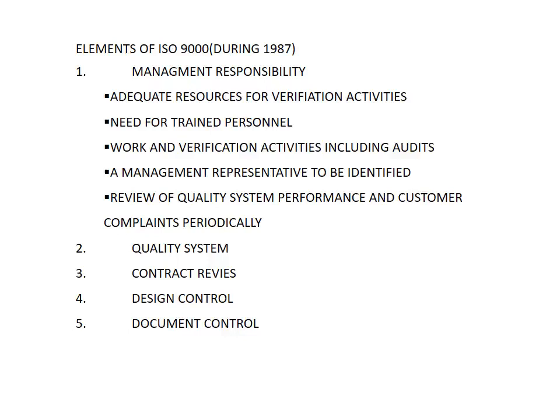The internal verification activity shall include the inspection, test and monitoring of design, production, installation, servicing, process, quality system, and design review. These activities shall be carried out by independent or trained persons not related to the activity. So the persons performing those activities are not doing the audit; it is verified by persons from another department.